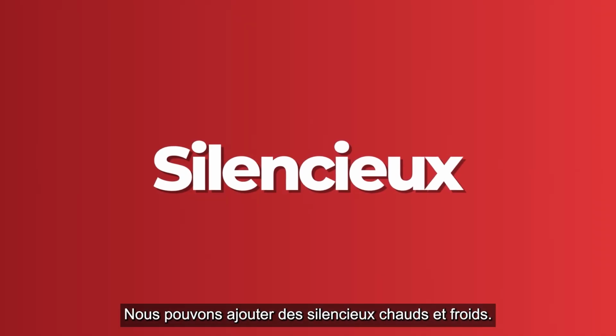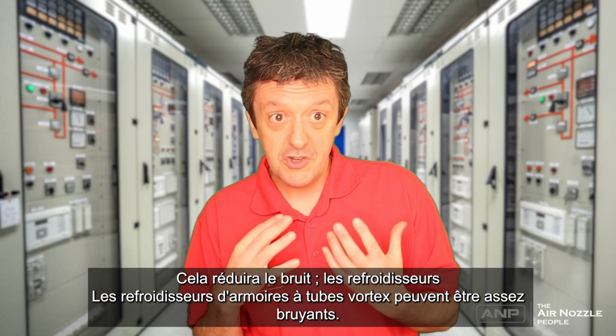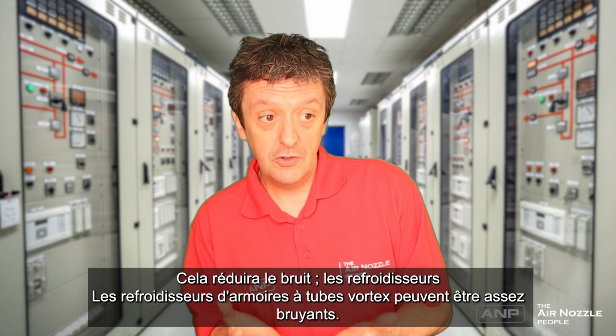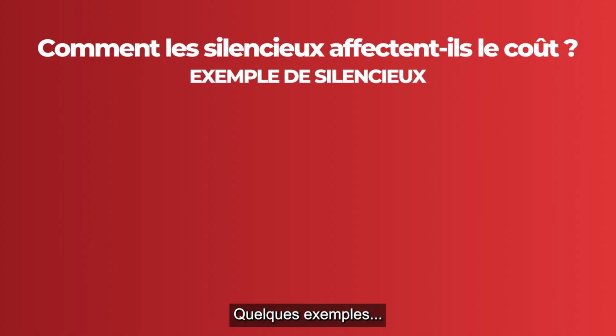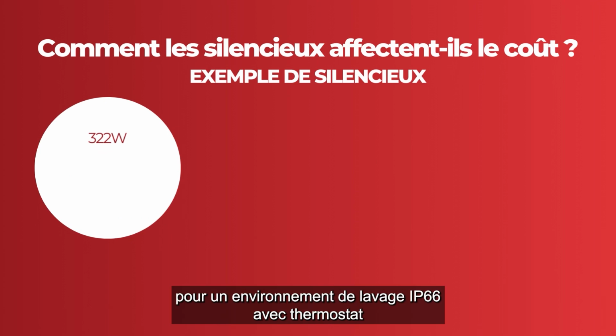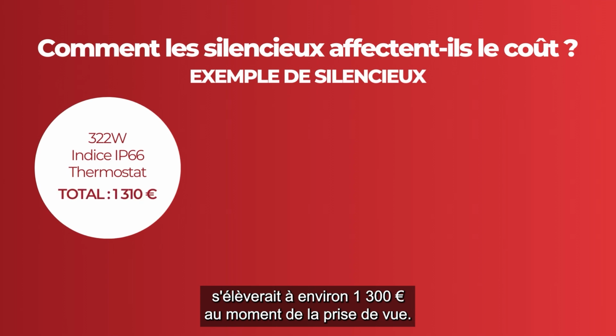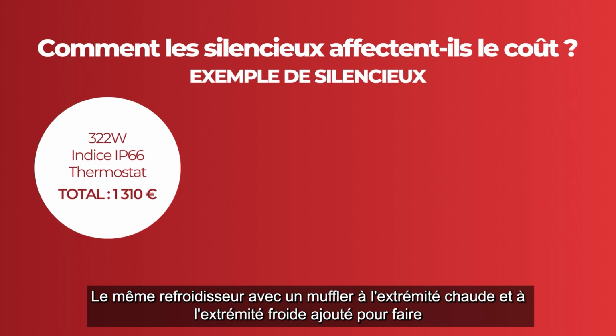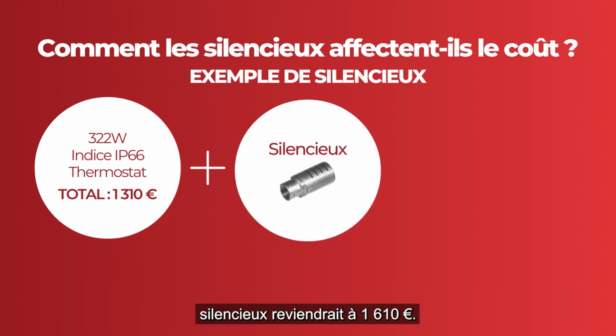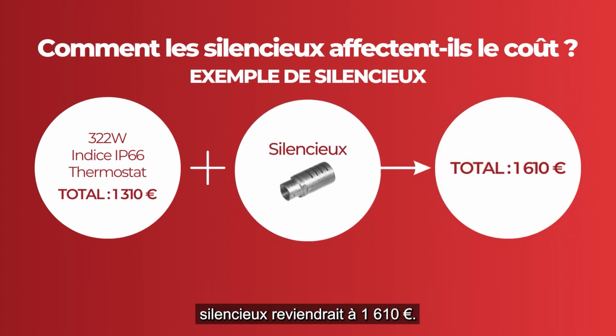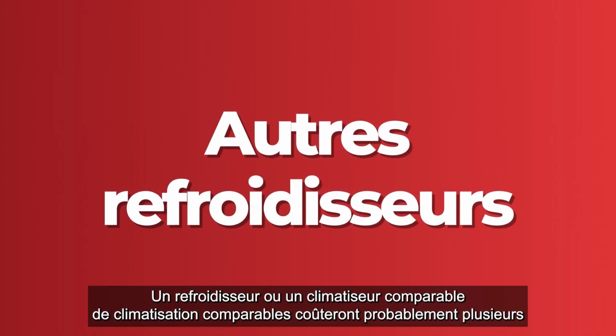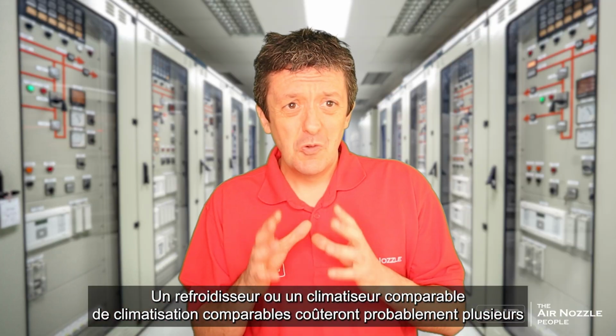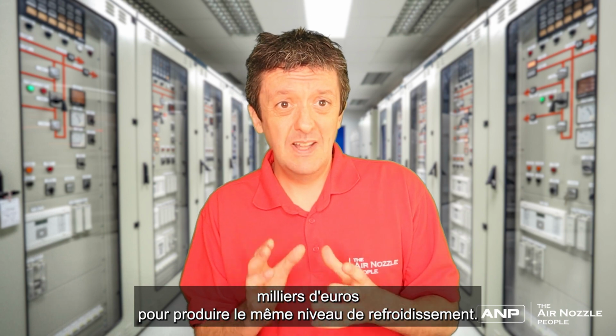We can add hot and cold end mufflers. This will reduce the noise. Vortex Tube cabinet coolers can get quite noisy. Some examples: a 322 watt cooler for an IP66 or washdown environment with a thermostat would be about £1,125 at the time of shooting. The same cooler with a hot and cold end muffler added to make it quiet would be £1,383. A comparable chiller or aircon unit is likely to cost several £1,000s to produce the same level of cooling.